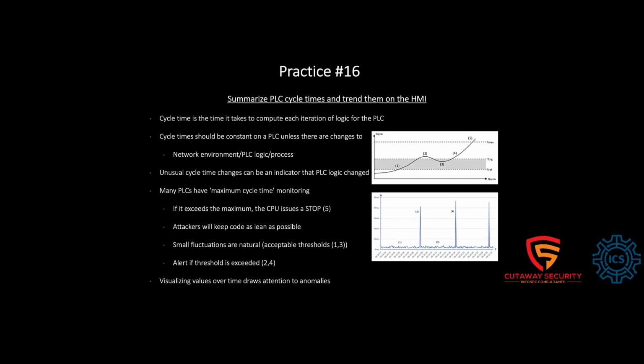So isn't this something that's already in the data historian? Everything that's going on in the PLC should be passing back there. At least, if you haven't programmed PLCs and don't know about these environments, you would expect everything to be going back there. So is this typically something you would see or not see in the data historian's information, and it specifically needs to be added? Yeah, this is not usually seen in the data historian. Number one, this might not even get out of the PLC, so it might never be on the HMI. These cycle times, or there are other monitoring practices where we recommend monitoring the memory usage.